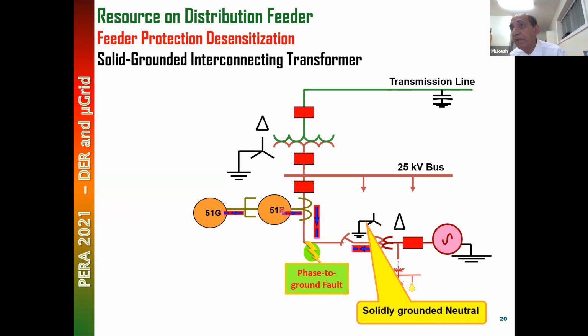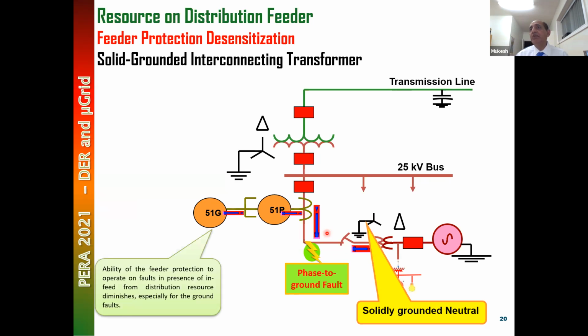So that's a trade-off. You do solid grounding, and the reason I say there's a fault resistance here: the fault resistance happened to be here, and the current coming from here, even both of them may not be able to see. Neither of them may be able to see. So how do we overcome this challenge? There could be a middle way.